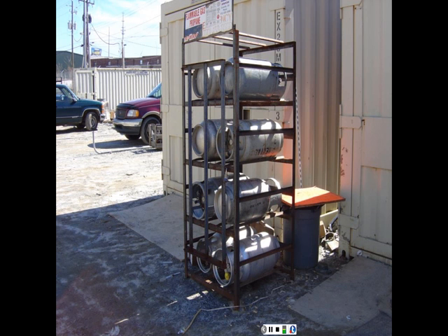So here, for example, we have a proper storage outside of the building with a proper clearing space. This is a temporary storage, by the way. It's not a permanent building, and it has all the warnings outside. And it's properly locked to prevent any inadvertent use of these tanks.